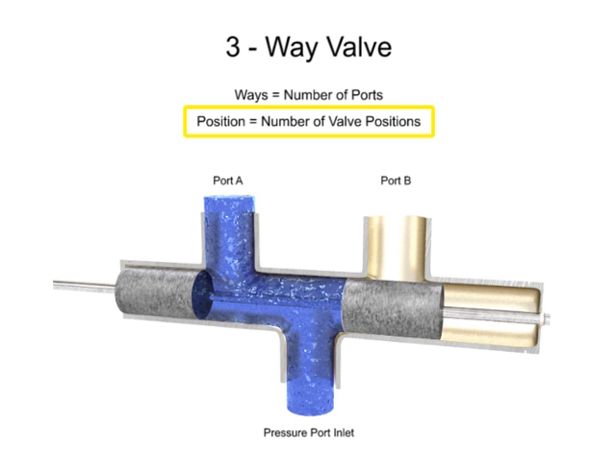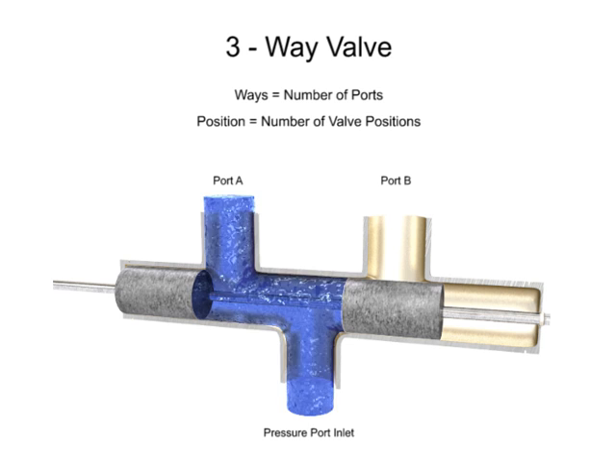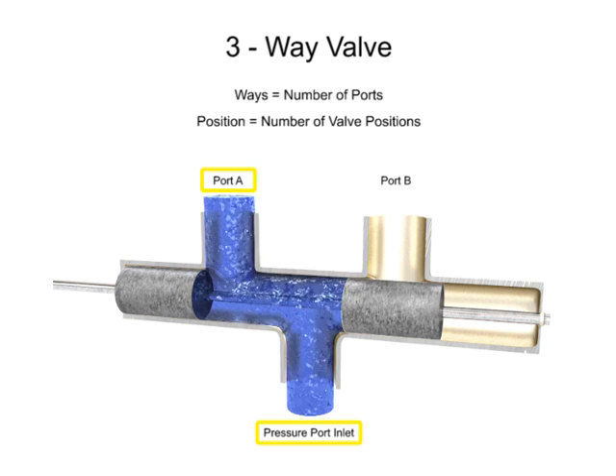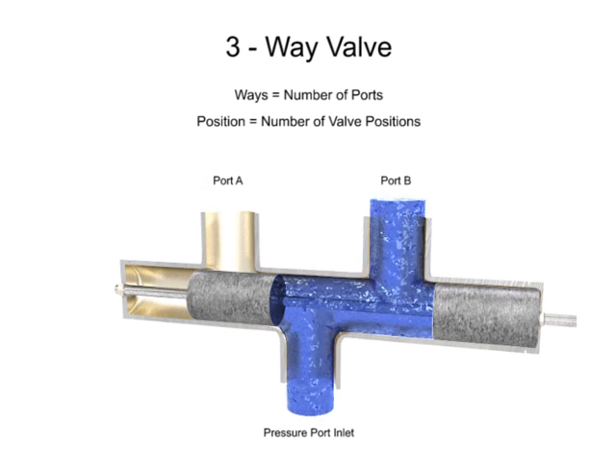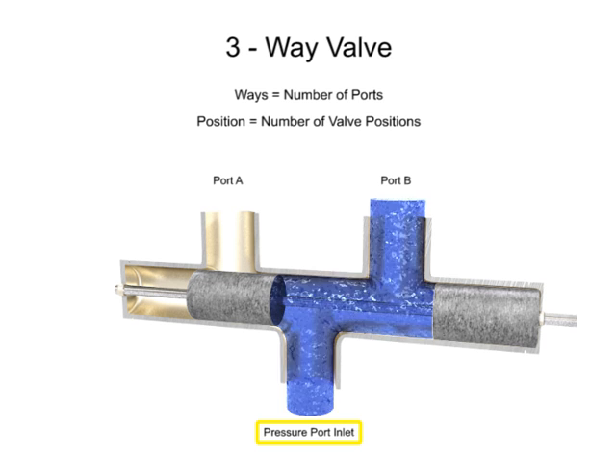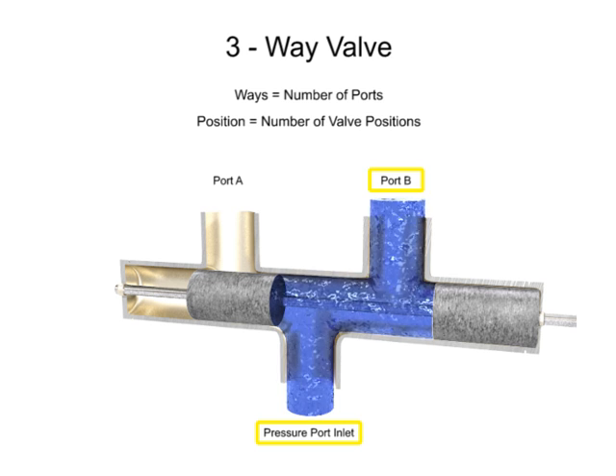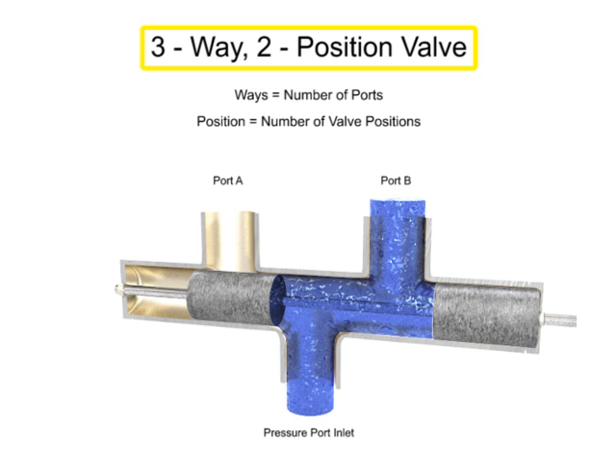The term position refers to the number of discrete operating positions of the internal valve element. For this spool valve, one position allows fluid to flow from the inlet to port A and a second position allows fluid to flow from the inlet to port B. Therefore, this is a two-position valve.